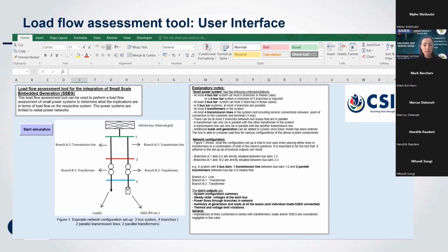And then other limitations of the tool are that you can have at most 2 transformers, or you can have at most 4 transmission lines in your system. Also a transmission line can only be in parallel with another transmission line as is shown on the tool here, or the transformers need to be in parallel with each other if you've got two parallel transformers. And then you would have your external grid connected to that, and you can enter your parameters for your external grid, which would be obviously an aggregation of your municipal network where you would like to do your study.